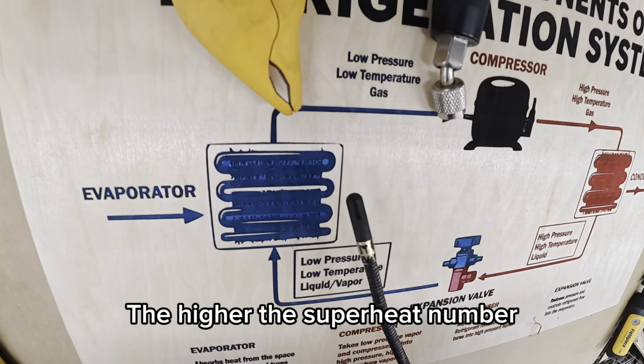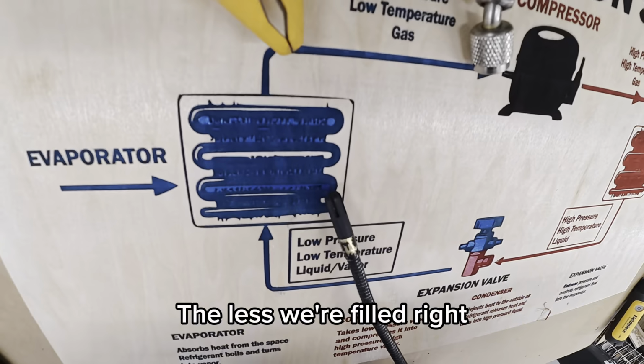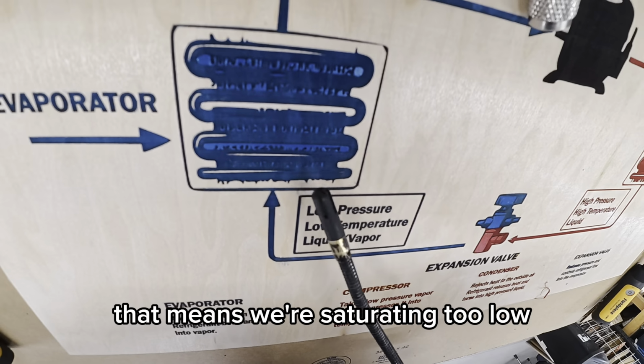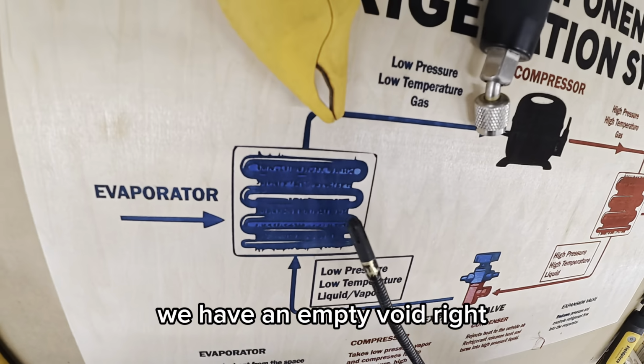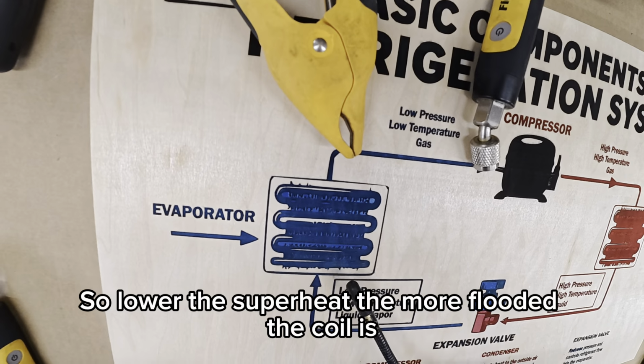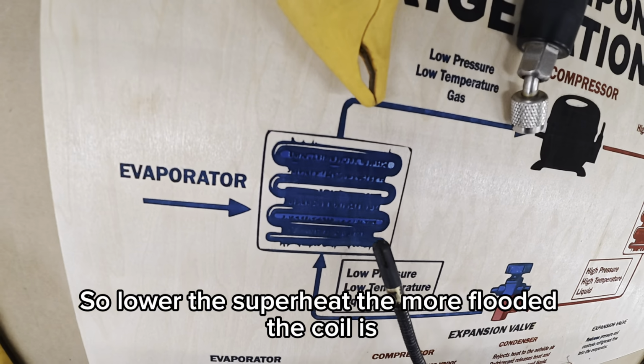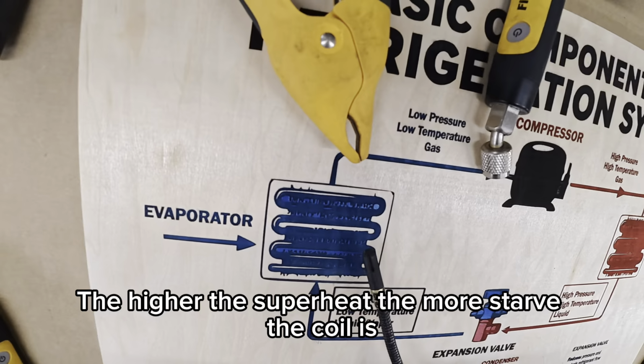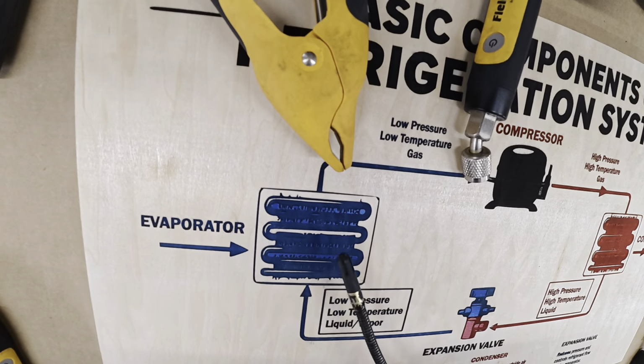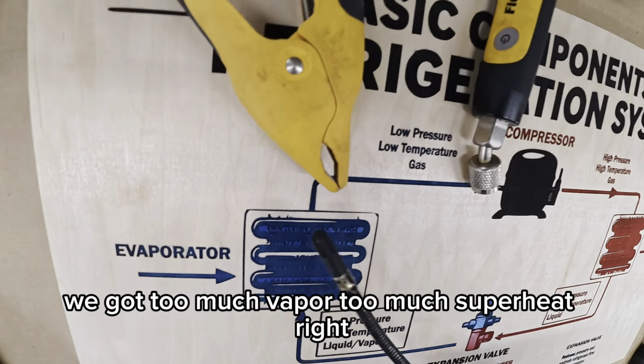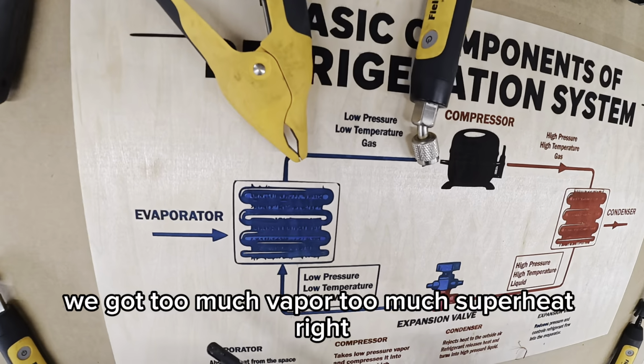The higher the superheat number, the less we're filled, right? That means we're saturating too low, we have an empty void. So the lower the superheat, the more flooded the coil is. The higher the superheat, the more starved the coil is. That means we're boiling it off too fast, we've got too much vapor, too much superheat, right?